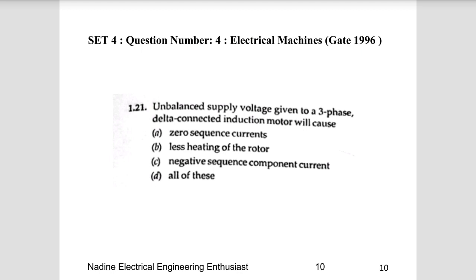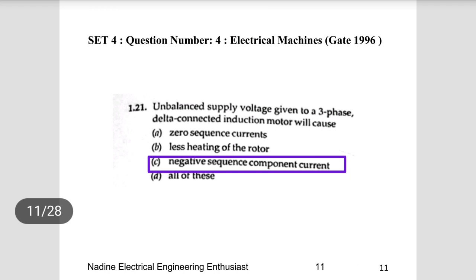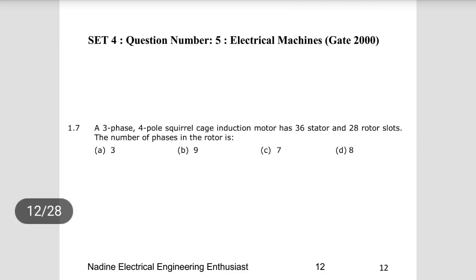Question 4: An unbalanced supply voltage given to a three-phase delta connected induction motor will cause what? An unsymmetrical voltage can be decomposed into positive sequence, negative sequence, and zero sequence components. An unbalanced supply voltage will normally have a negative sequence component, while earth fault values carry a zero sequence component. So Choice C is the right answer: it causes a negative sequence component current.